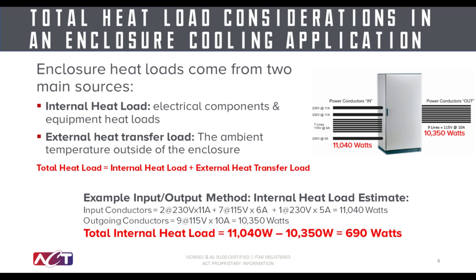As you can see at the bottom of this slide, here's one example where we're taking 2 input conductors at 230 volts and 11 amps, 7 input conductors at 115 volts, 6 amps, and 1 input conductor at 230 volts, 5 amps to find a total incoming heat load of 11,040 watts. The outgoing conductors can be calculated in a similar fashion, with 9 of them at 115 volts and 10 amps for a total of 10,350 watts. Taking the difference of these two values, we calculate the total internal heat load to be 690 watts.